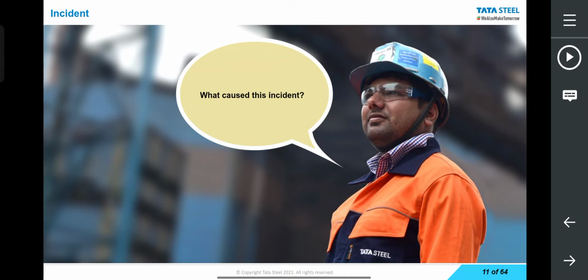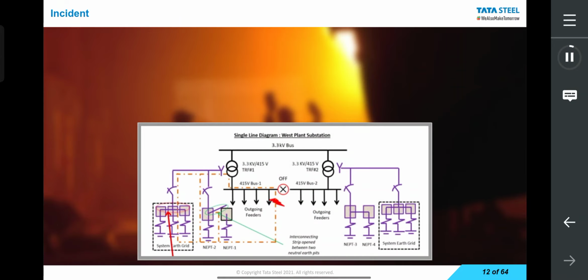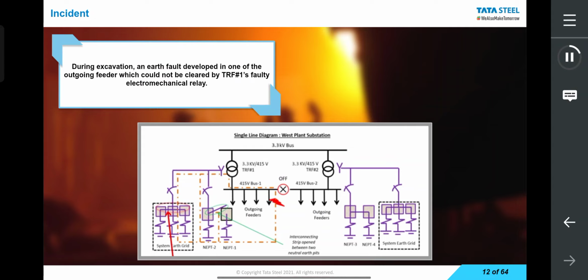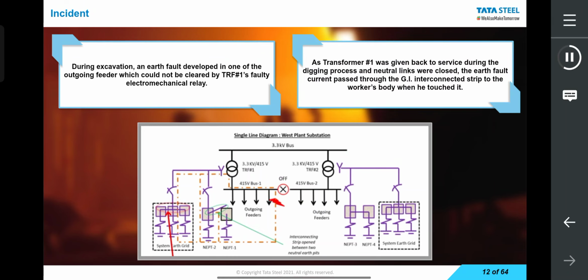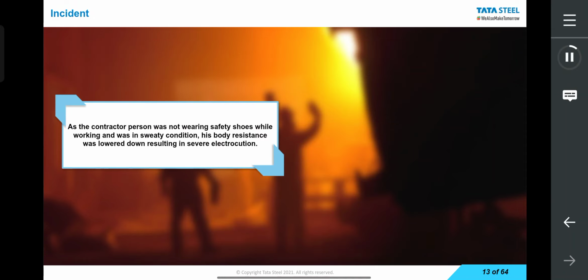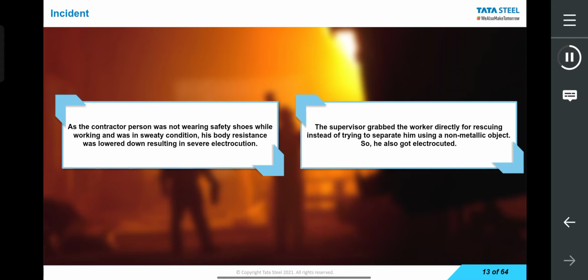Do you know why this happened? This happened because of the following reasons. During excavation, an earth fault developed in one of the outgoing feeder which could not be cleared by transformer 1's faulty electromechanical relay. As transformer 1 was given back to service during the digging process and neutral links were closed, the earth fault current passed through the GI interconnected strip to the worker's body when he touched it. As the contractor person was not wearing safety shoes while working and was in sweaty condition, his body resistance was lowered down, resulting in severe electrocution. The supervisor grabbed the worker directly for rescuing instead of trying to separate him using a non-metallic object. So, he also got electrocuted.